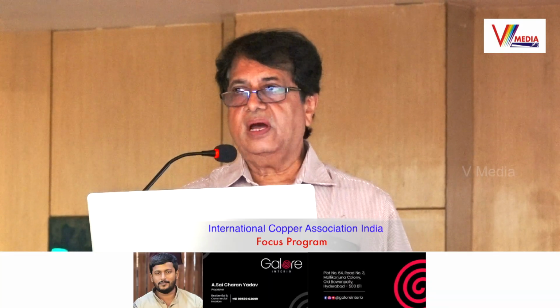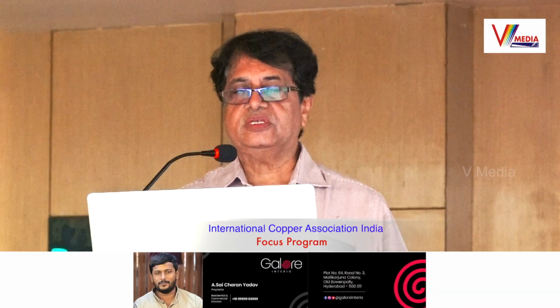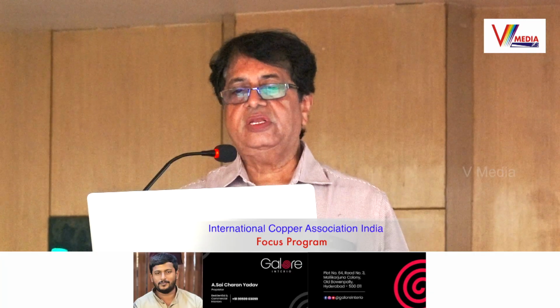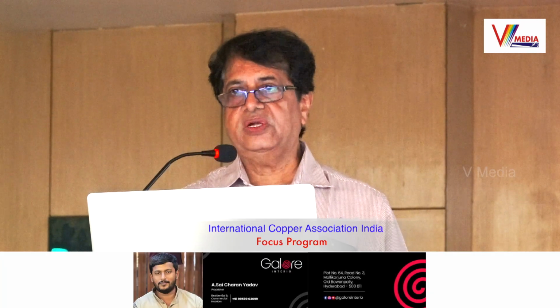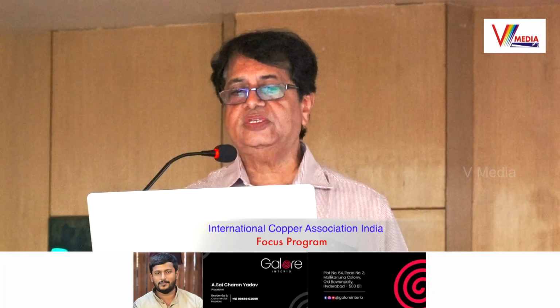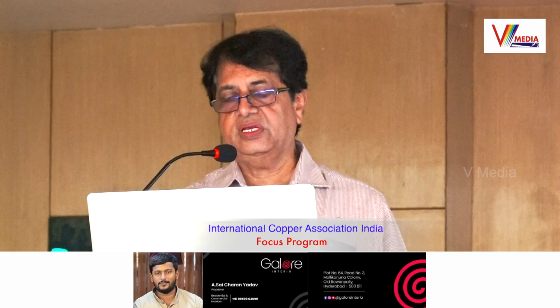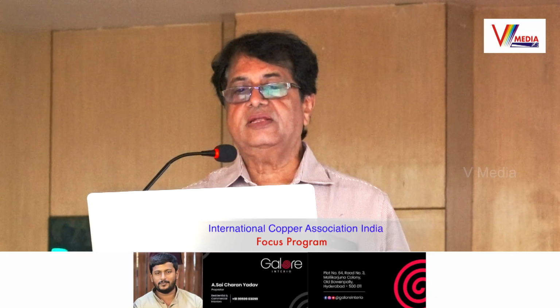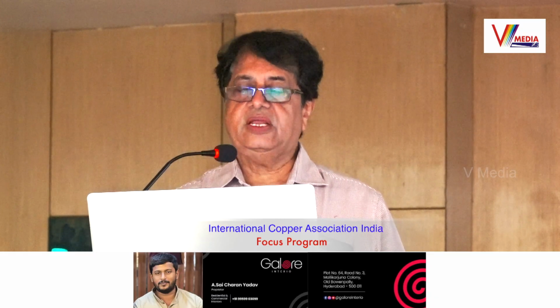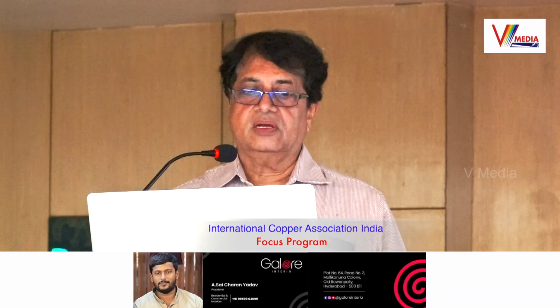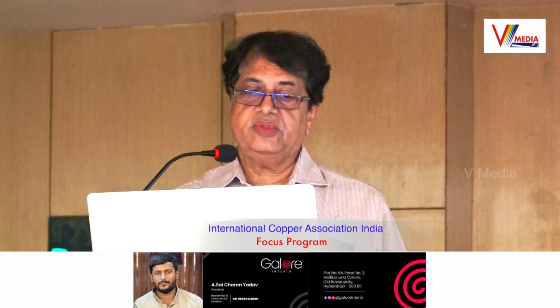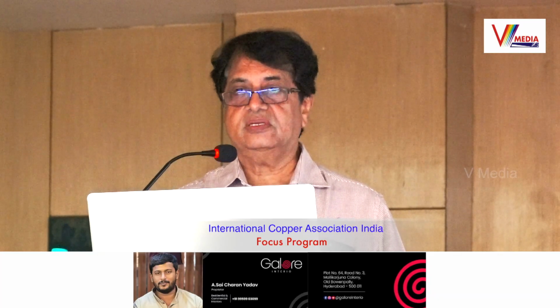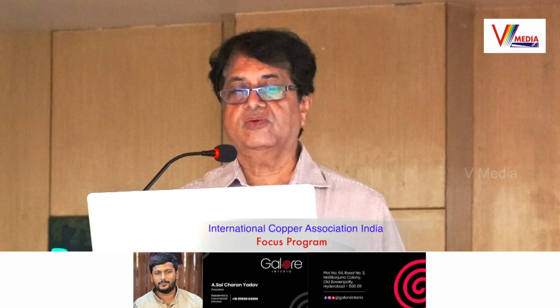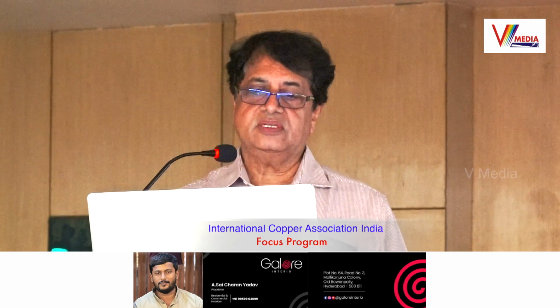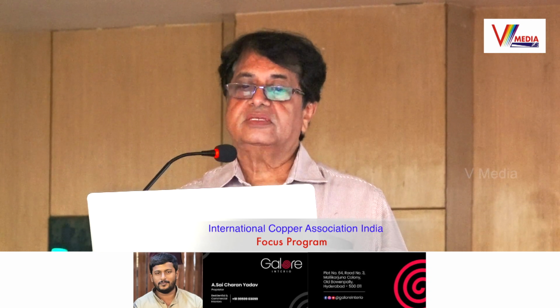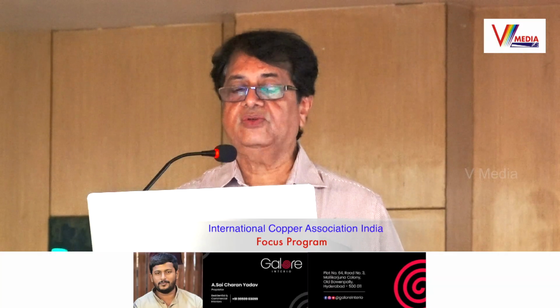You have to plan the underground services within the complex of the building very precisely. For different types of services, there should be some clearances which are mandated in the regulations. Between electrical line to electrical line, what should be the clearances between electrical power cable and control cable, what should be the clearances between power cables and the communication line or the underground water pipelines, that is given in the CEA regulations.